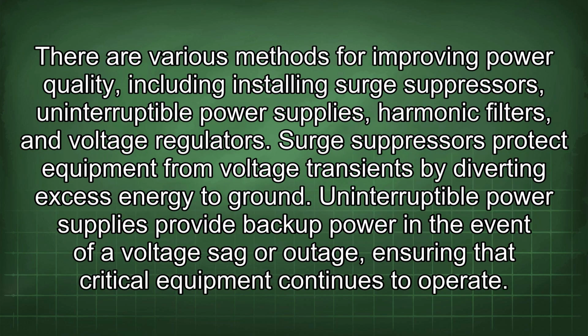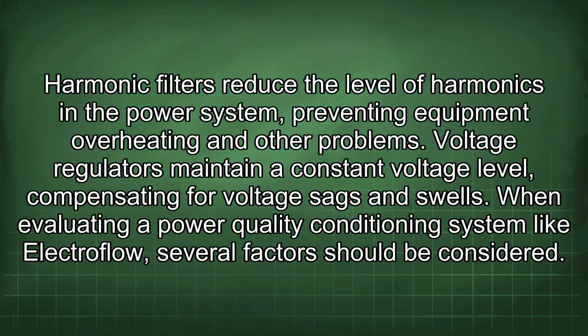There are various methods for improving power quality, including installing surge suppressors, uninterruptible power supplies, harmonic filters, and voltage regulators. Surge suppressors protect equipment from voltage transients by diverting excess energy to ground. Uninterruptible power supplies provide backup power in the event of a voltage sag or outage, ensuring that critical equipment continues to operate. Harmonic filters reduce the level of harmonics in the power system, preventing equipment overheating and other problems. Voltage regulators maintain a constant voltage level, compensating for voltage sags and swells.